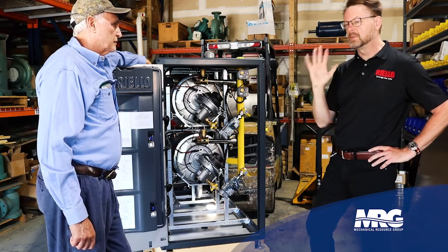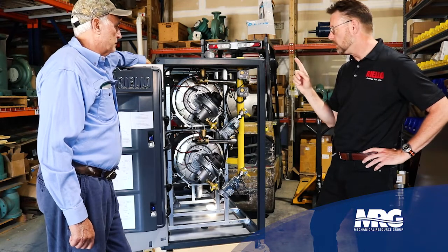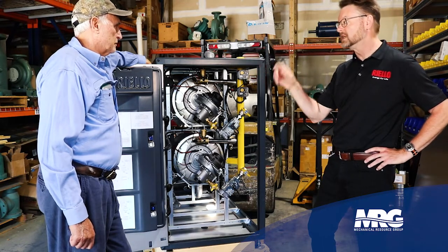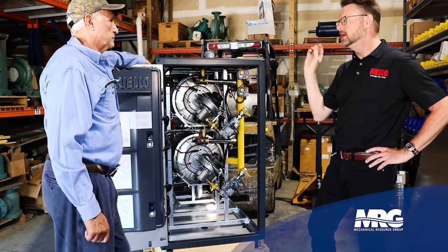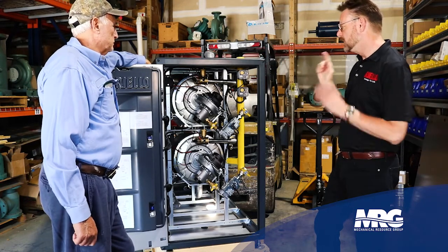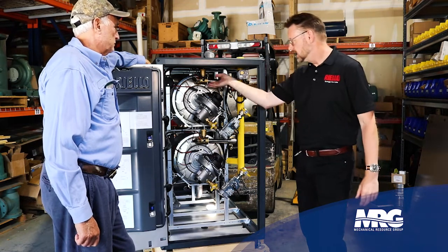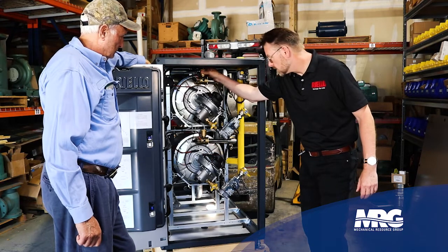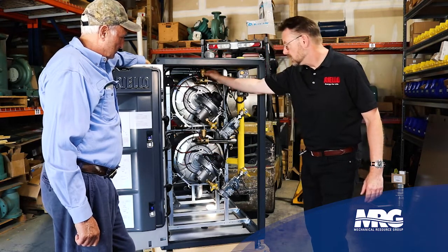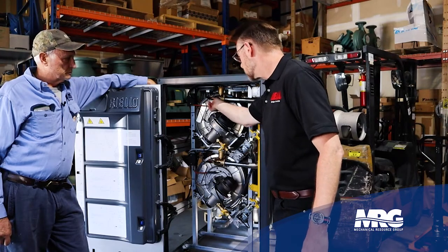So we're going to have a couple of opportunities to introduce a low water cutoff challenge. If the low water cutoff failure was the device, there was air stuck in the top of the heat exchanger. That could occur at 3 different places on this appliance, in fairness. If it occurs here, or here, because of perhaps the failure of this air vent to operate, that's going to airbound, and that's going to result in this low water cutoff tripping.